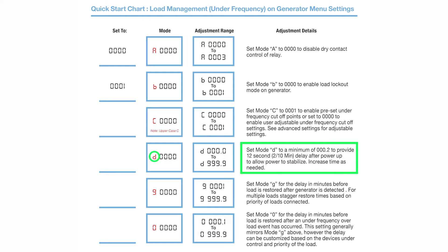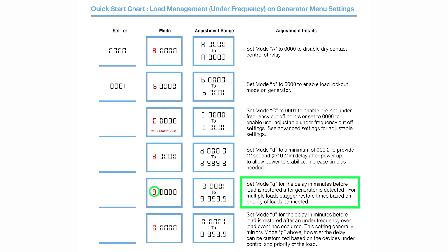Menu D should be set to 0.2 for a 12 second startup delay. Menu G should be set to 2.5 for your highest priority load. This will provide a two and a half minute delay before the load is restored after generator power has been detected.